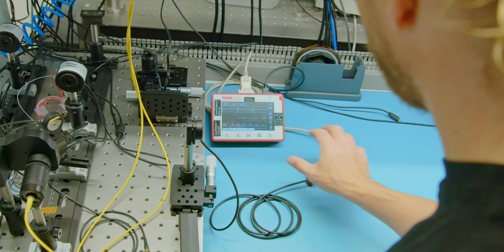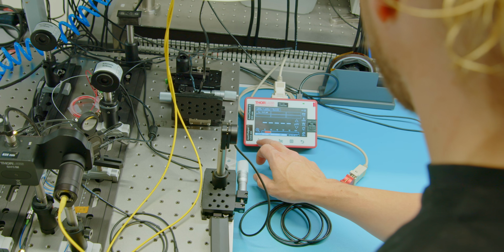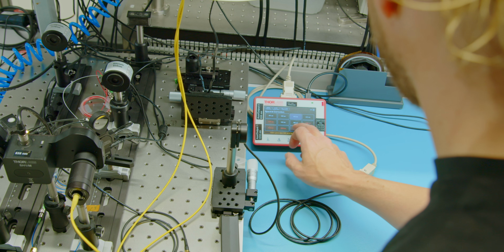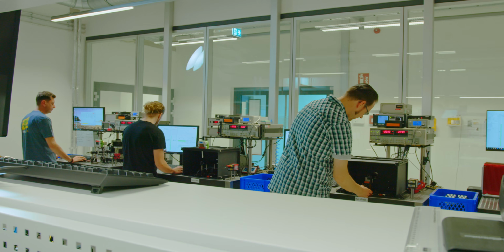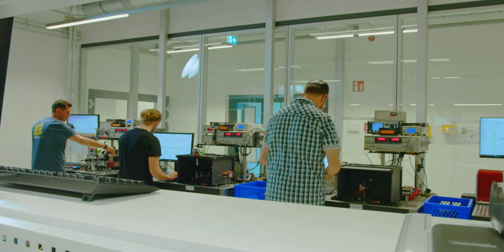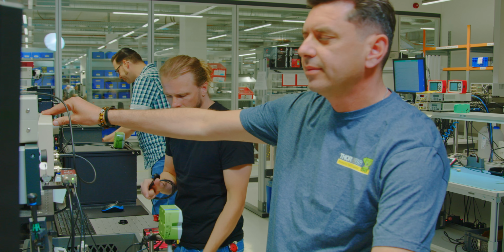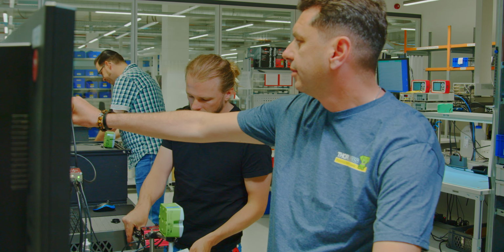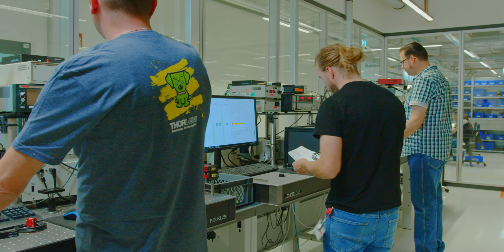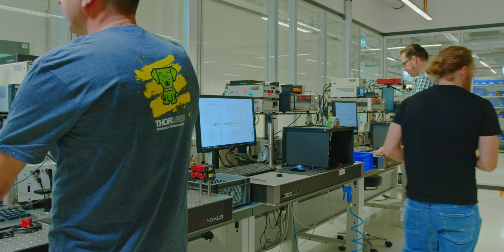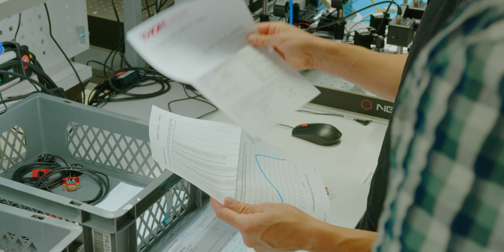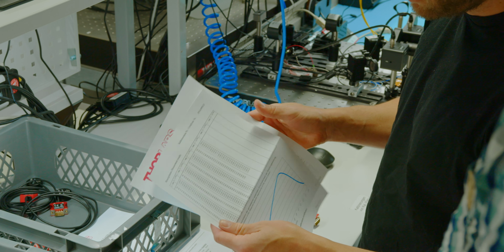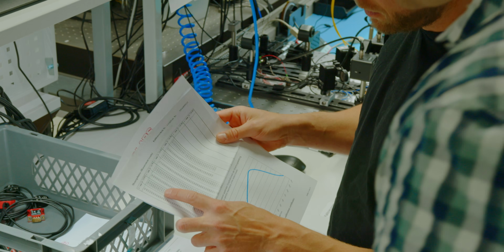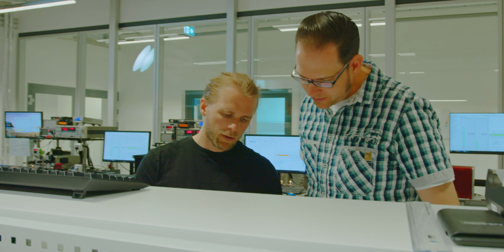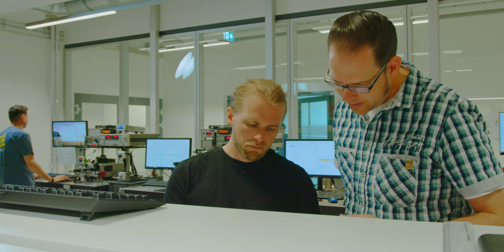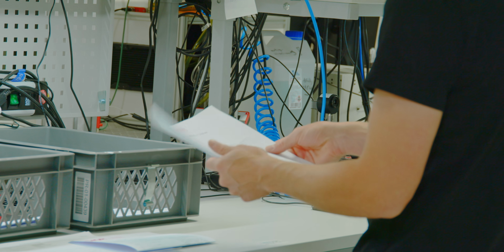For example, any factory standard in which test equipment is calibrated and also has to be validated by a DAkkS certificate. It is also suitable for users who are ISO certified and follow other industry-specific quality guidelines that must be traceable to national standards or also international standards. And only the accredited calibration certificate is suitable as a proof of traceability.